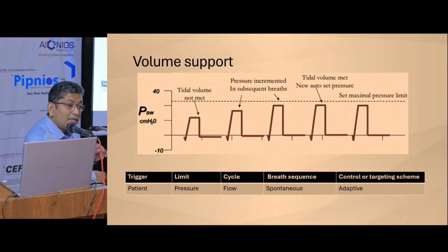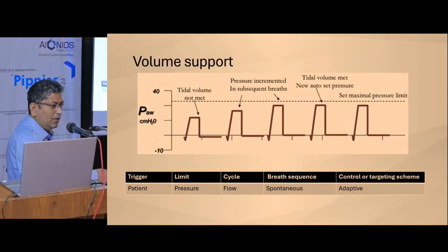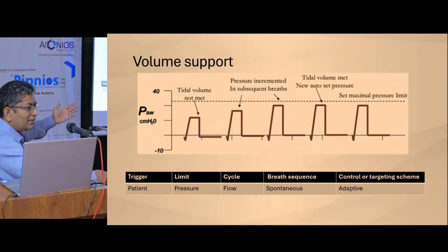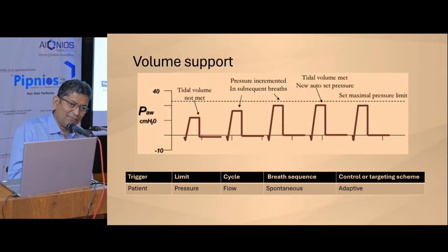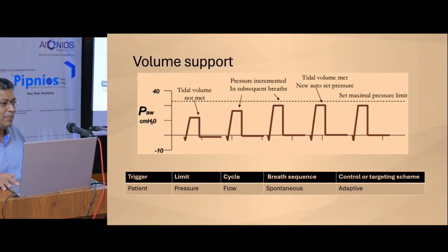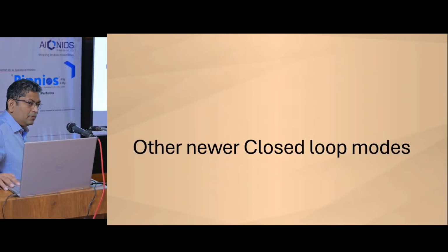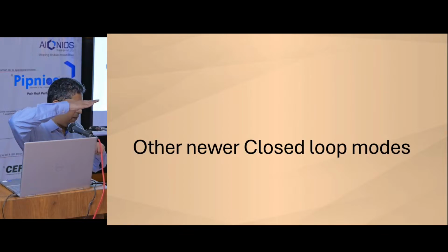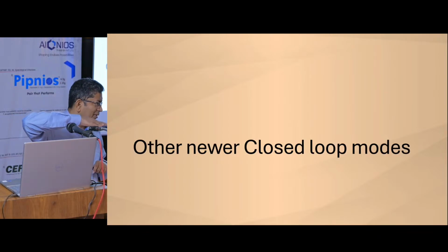Here the breath cycle is spontaneous because there's no machine timer here. It's only the patient timer, and the cycle is also flow, so it's spontaneous. And the targeting scheme here is also adaptive. So that's the difference between volume support and PRVC, or adaptive pressure control. Okay, so you got an idea of how the adaptive thing works, right?